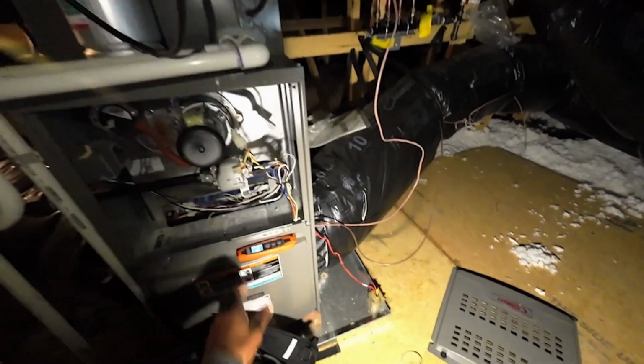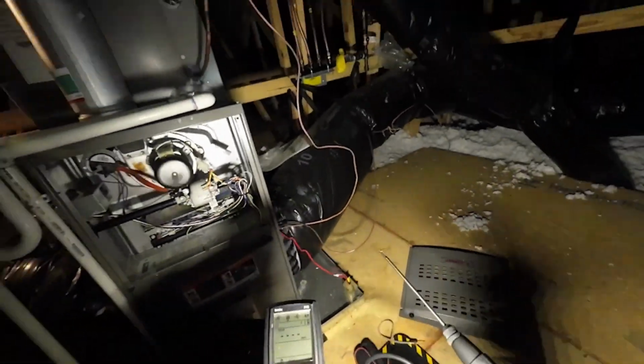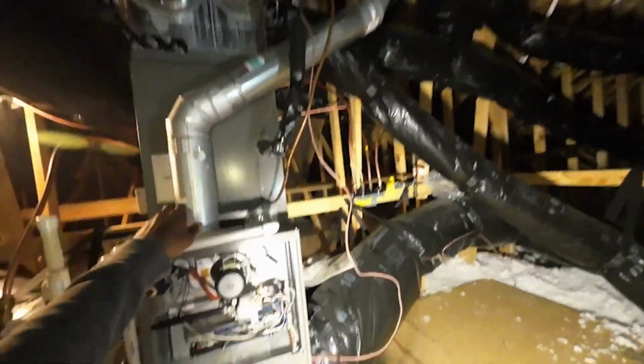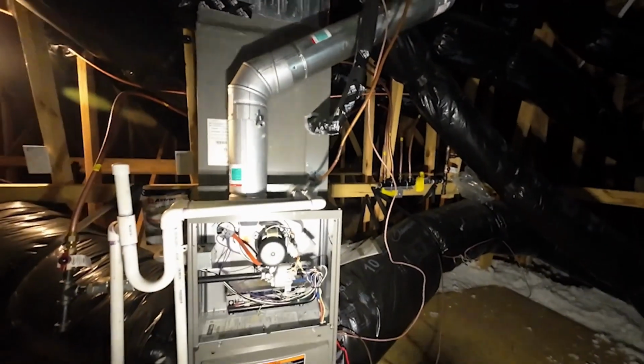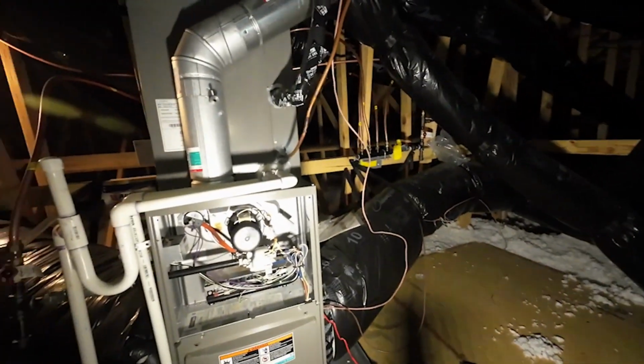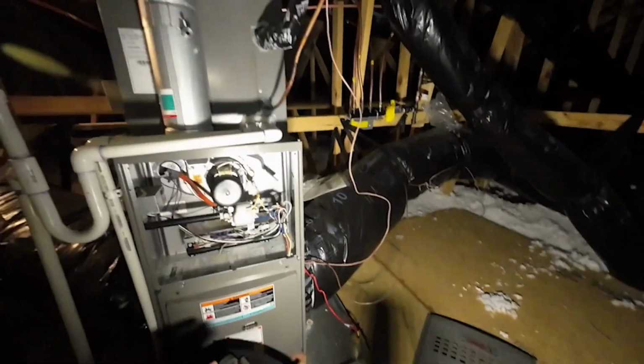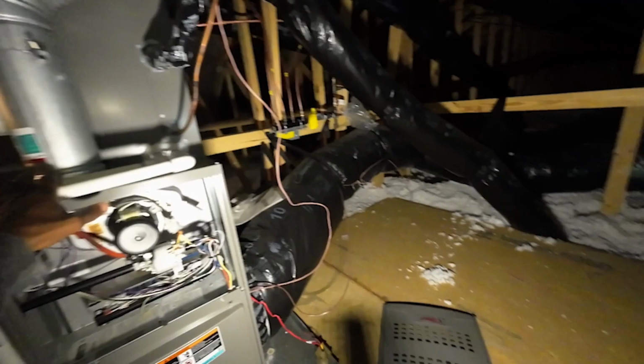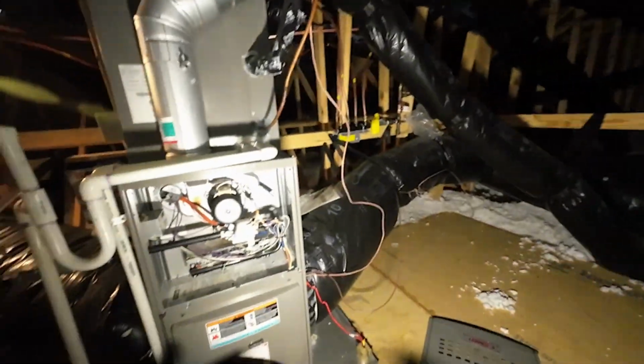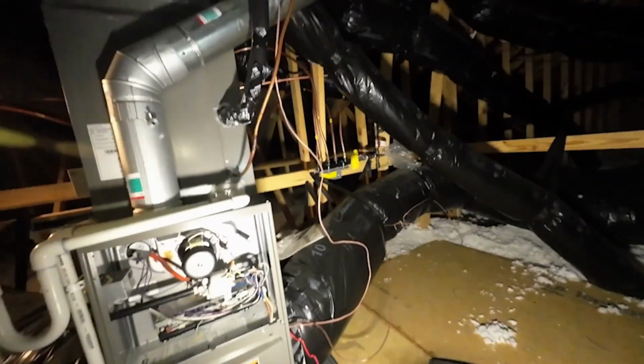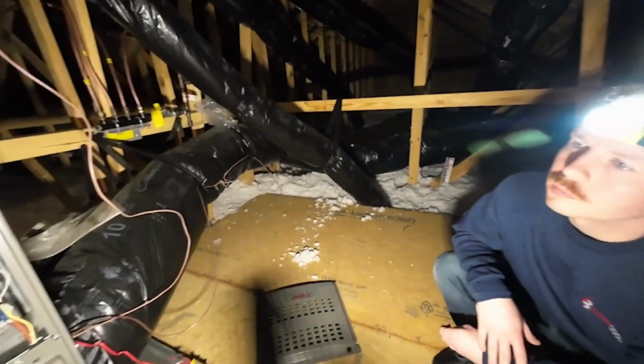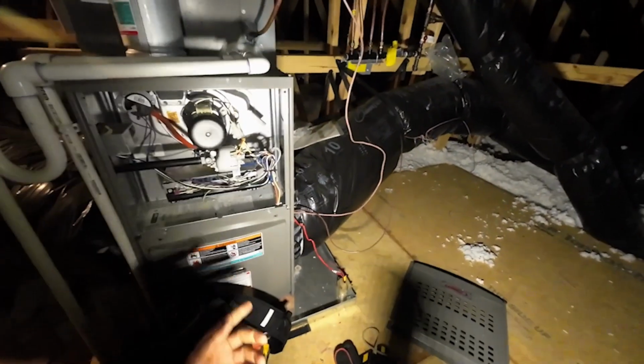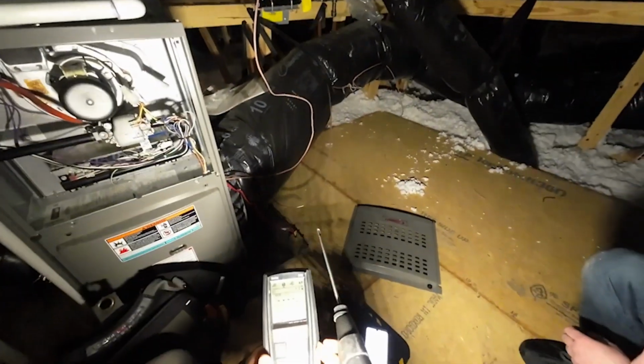So I'm just going to go ahead and let that stabilize a bit. I'm going to go ahead and check the draft pressure, which is the amount of draft. This is a negative pressure in here, meaning that the pressure in this pipe is actually lower than the pressure that we're standing in right now. The reason why is because it's inducing a draft in the flue pipe. That's why it's called an induced draft motor. It's not pressurizing the pipe, it's just making it so that hot air is rising in there. Heat rises, so the velocity, the speed of that hot air rising is pulling in the air behind it, causing a negative pressure, if that makes sense.